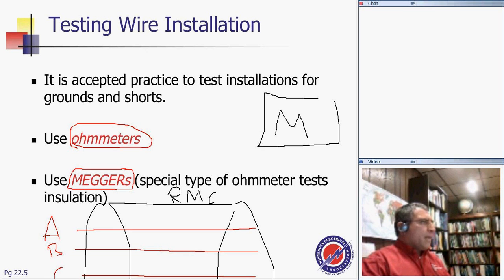It has a battery, and you charge it, and off you go with the lead. Let's use this as a lead. So take one lead here. You're going to take it from phase A to the conduit. The insulation is intact, good. Then you should read very high resistance, extremely high. Then the insulation of phase A is perfect.